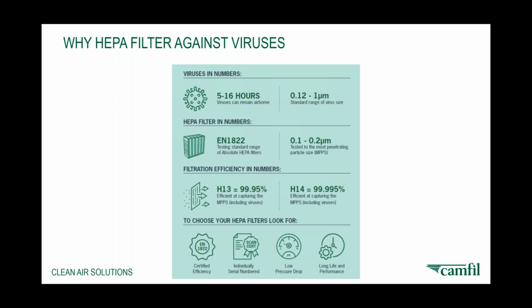A HEPA filter, by the numbers, according to the EN 1822, which is the standard for testing HEPAs or absolute HEPA filters. HEPAs are tested according to what's called the MPPS, or most penetrating particle size. And that tends to be between 0.1 and 0.2 microns. So it just happens to be similar in size to where most viruses tend to fall, or particularly COVID-19.